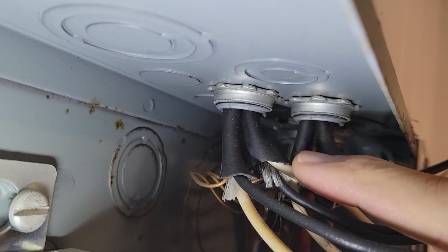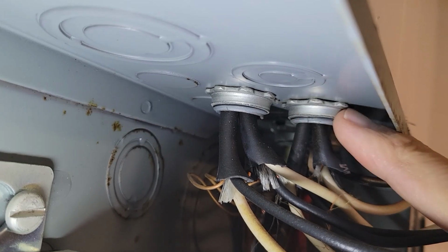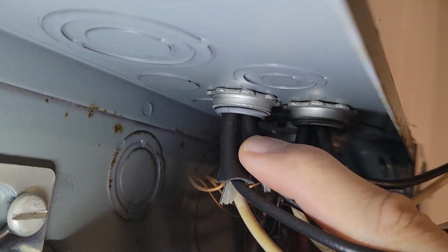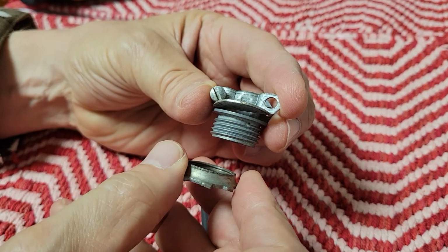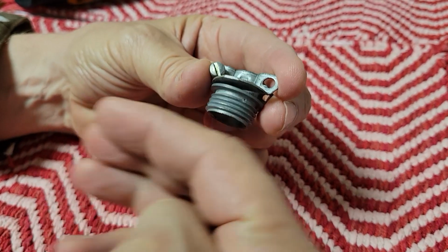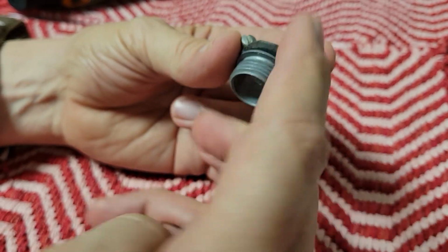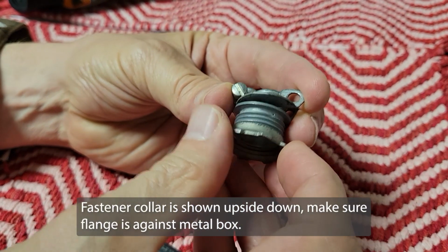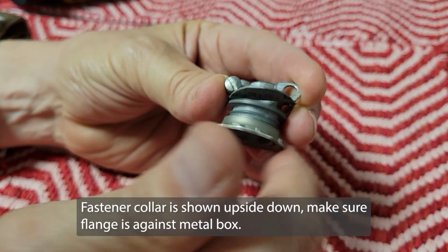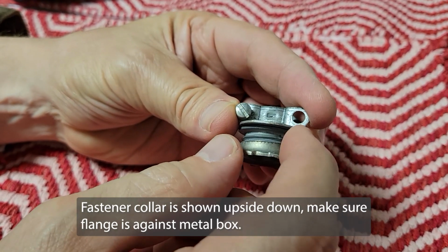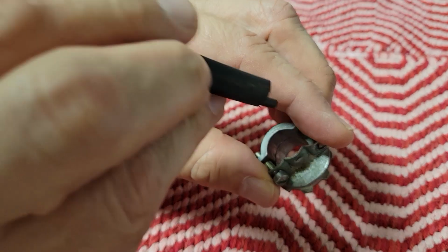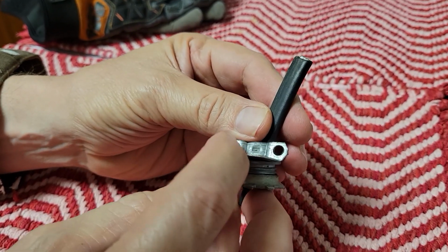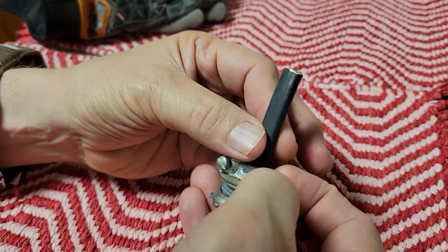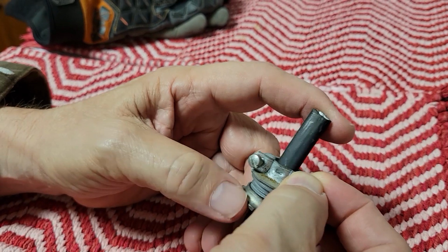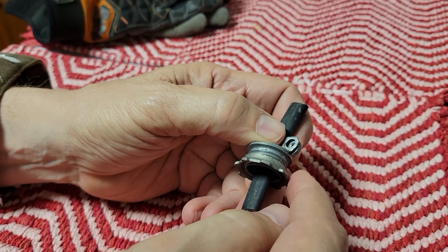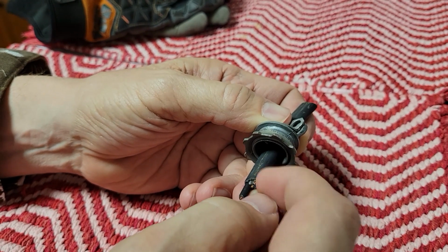All the cables coming into the sub panel go through an NM connector, for non-metal, for Romex cable like this, which is just sheathed in plastic. This part goes on the outside of the sub panel and comes through the knockout. You have this fastener that catches it, and you tighten it so it's held snugly into the sub panel. Your cable goes through this opening, and then you tighten the screws on both sides until the cable is snug. This does two things: it keeps the cable in place, and it keeps the sharp edges of the knockout from cutting into it.